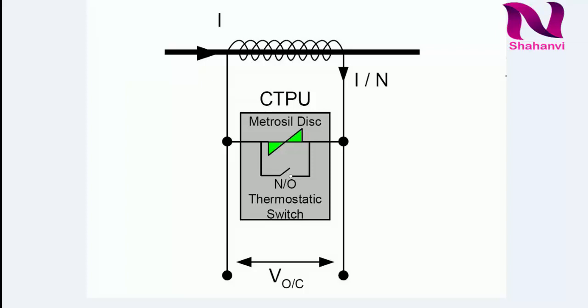My friends, now we will talk about its connection. The Metrosil current transformer protection unit should be connected across the secondary winding of a current transformer as close as possible to prevent it being inadvertently disconnected during maintenance.